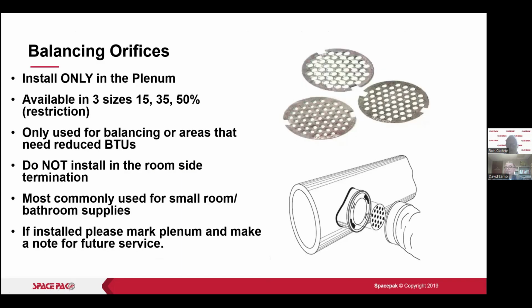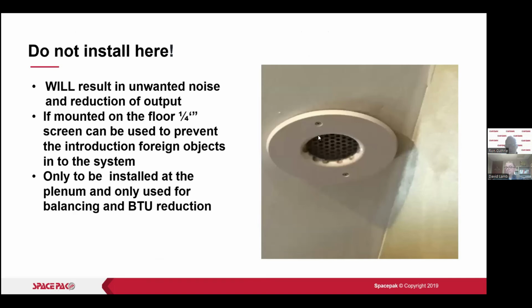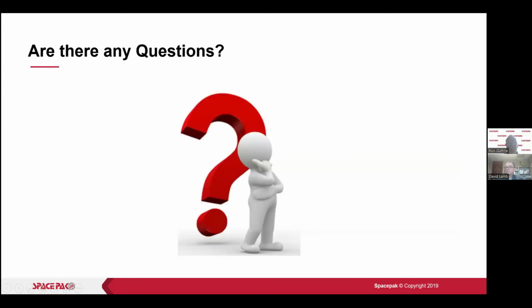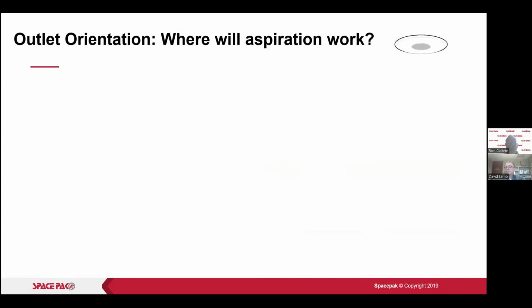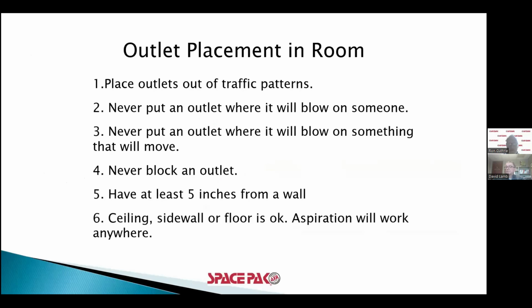We talked about that. You don't want to mount those balancing orifices here. It always gives that same pattern, it gets dirty, it adds pressure drop, and they're noisy. So these actually go back at the plenum takeoff. Again, outlets can face any direction. For placement in a room, don't block an outlet, and don't put it where there's going to be a piece of furniture. Common sense.